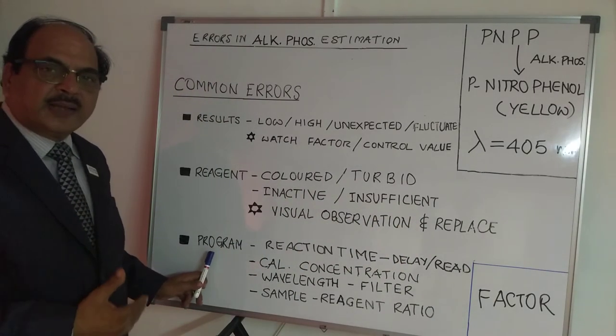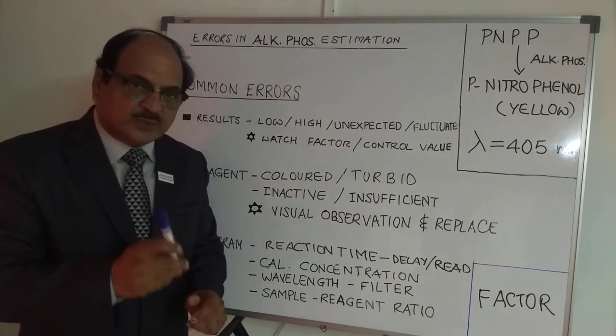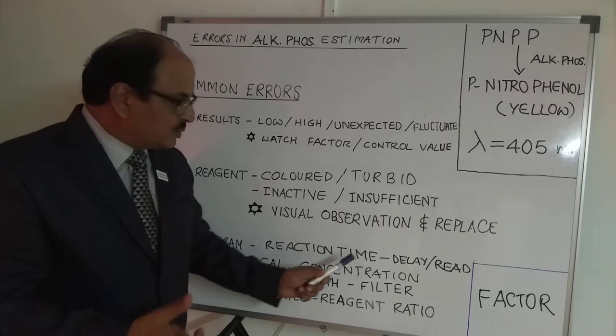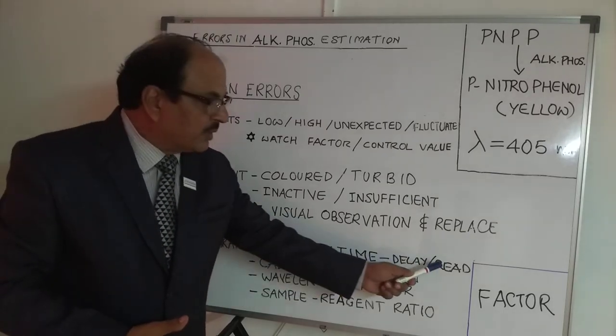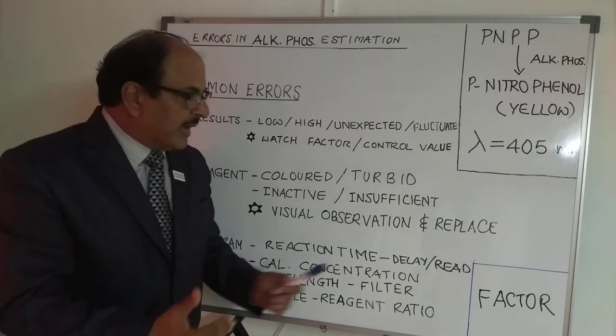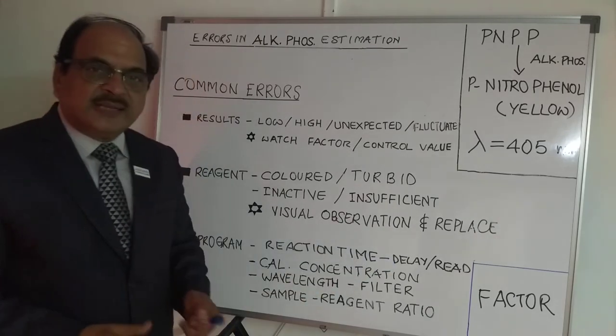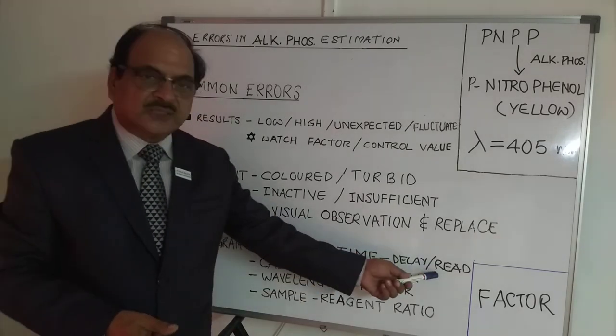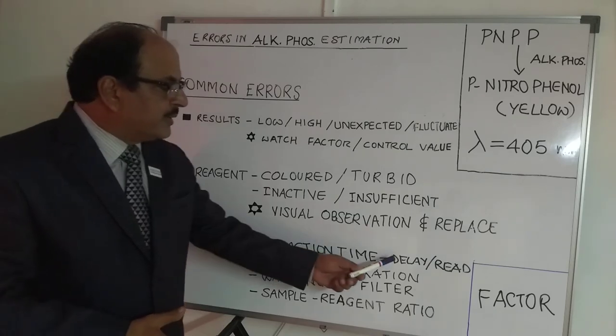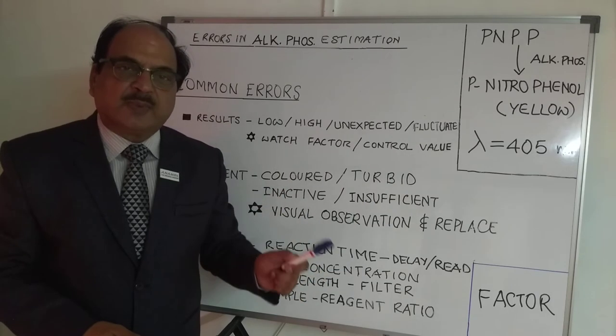The next category is program-related errors. Since this is a kinetic assay, it must have a reaction time, which you monitor in terms of two areas: the delay time and the read time. Delay time is the period before readings start after your reagent and sample are mixed. The read time is when the absorbance is measured during that period. Delay time is normally 60 seconds and read time is another 60 to 120 seconds, depending on what the manufacturer specifies. Ensure that your delay and read times are fed properly into the program as per the instruction manual.